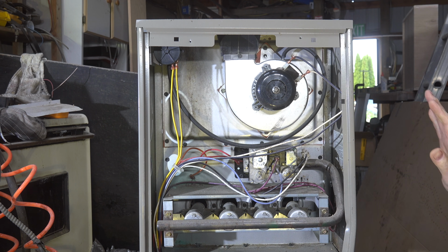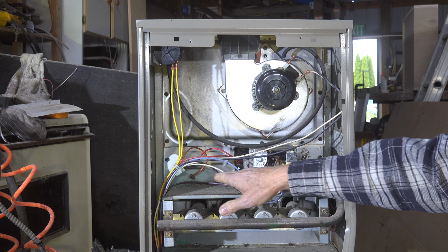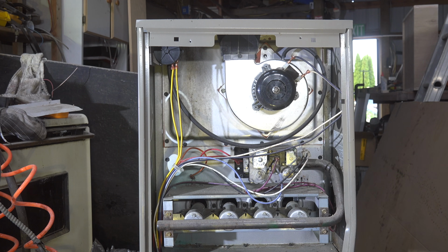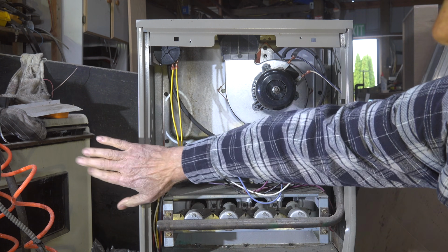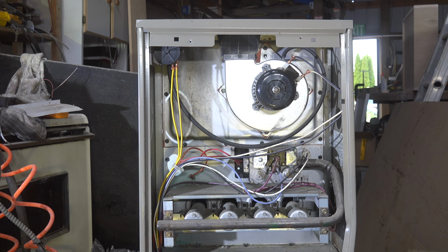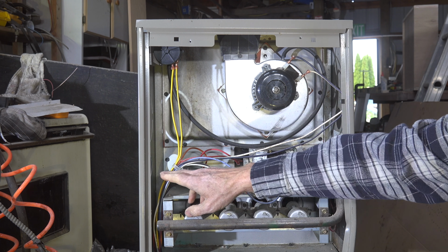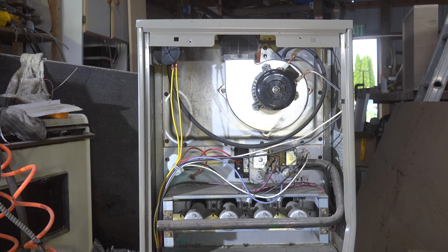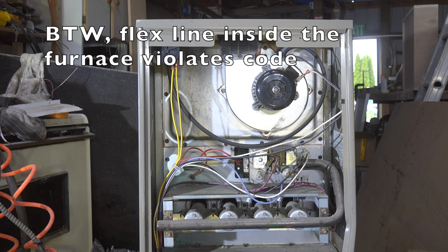If you get a new heat exchanger, I thought we'd go ahead and show you how to put this thing in with the least amount of trouble. Now, because this is a test mule, there's no piping here, but of course you're going to have to shut your gas off. There's going to be a gas cock out here somewhere, and of course you're going to shut your power off. Once you've done that, you're going to disconnect your piping. There may be a flex line coming in here, or there may be hard pipe and a union. All you have to do is break the union or break that flex line and get it out of the cabinet.